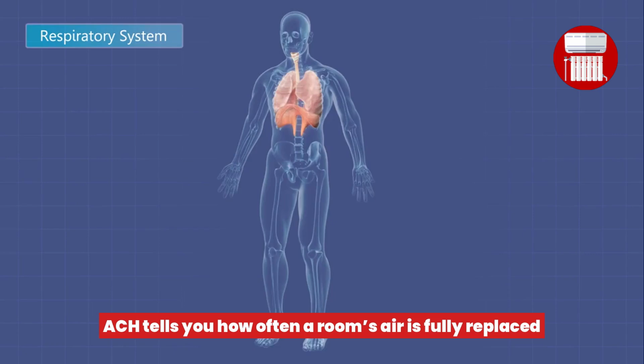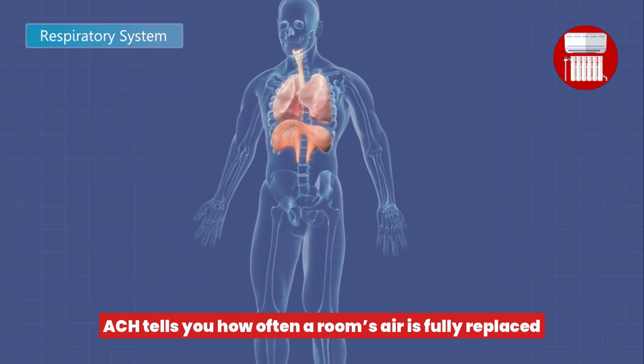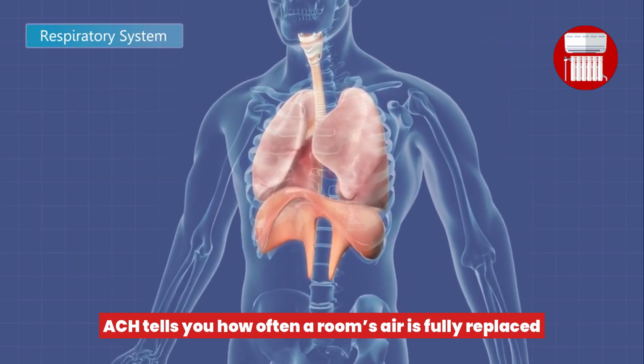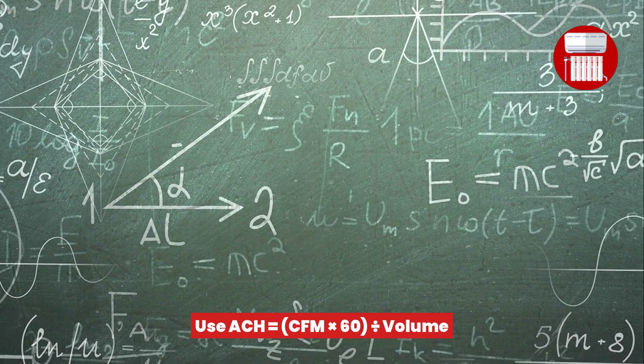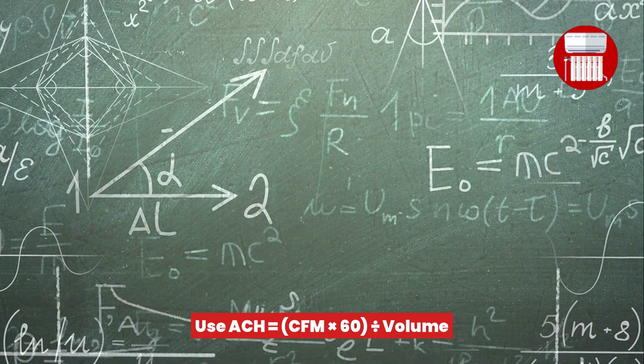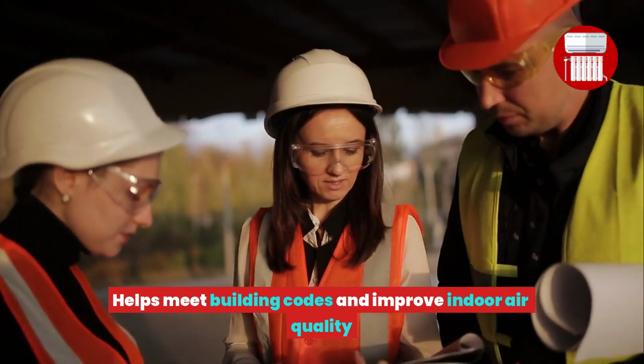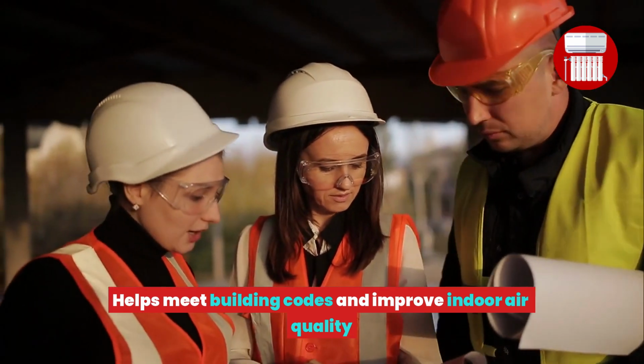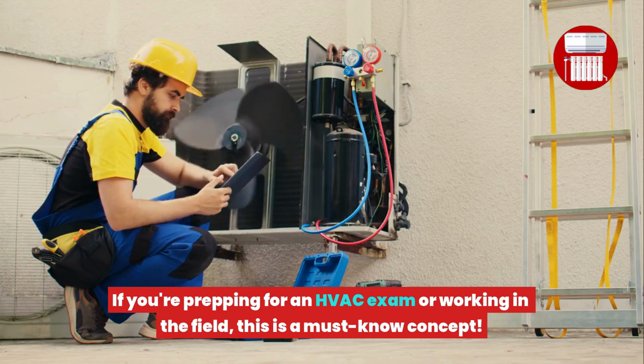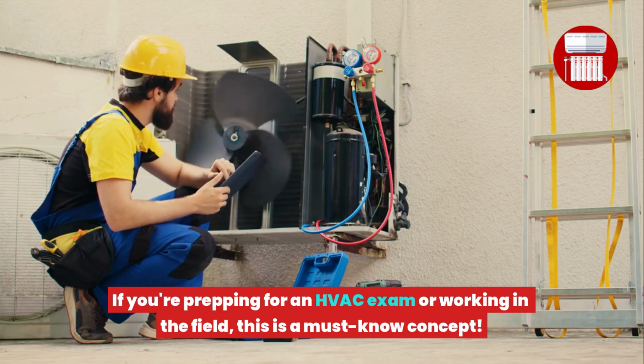Final recap. ACH tells you how often a room's air is fully replaced. Use ACH equals CFM x 60 divided by volume. Knowing it helps meet building codes and improve indoor air quality. If you're prepping for an HVAC exam or working in the field, this is a must-know concept.